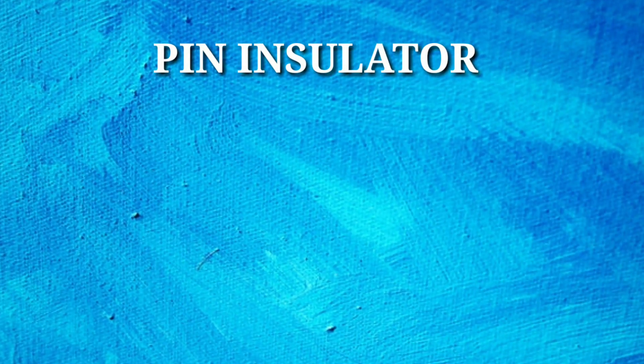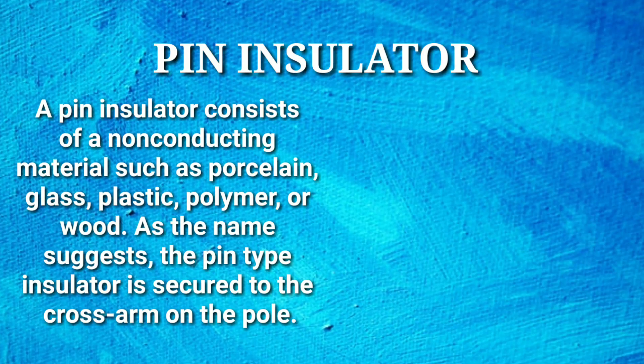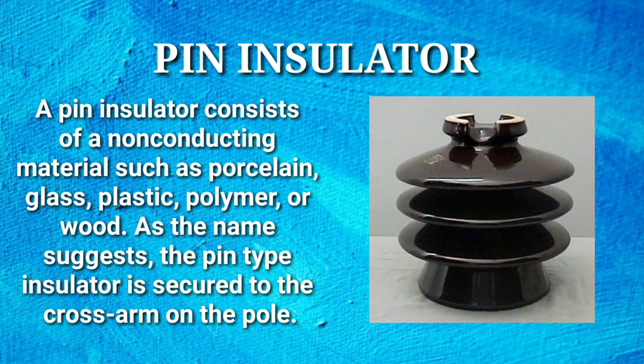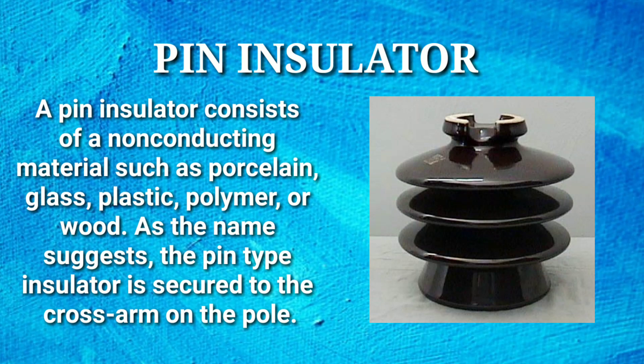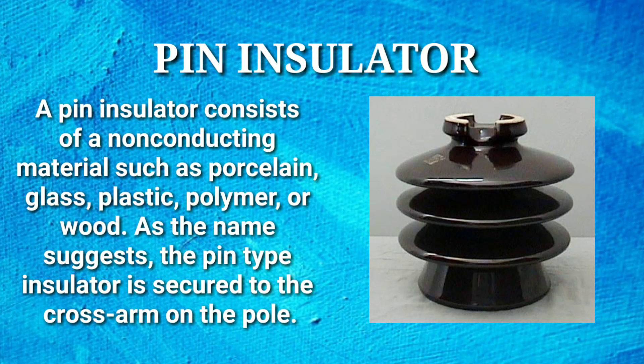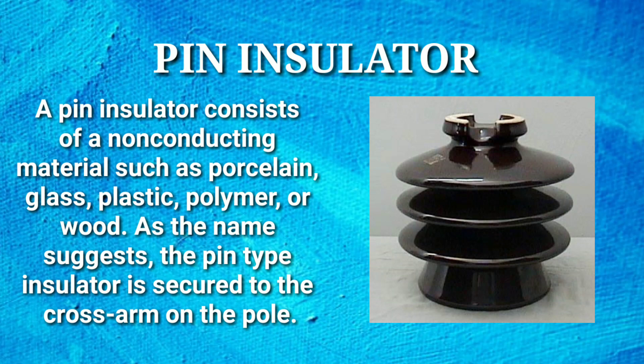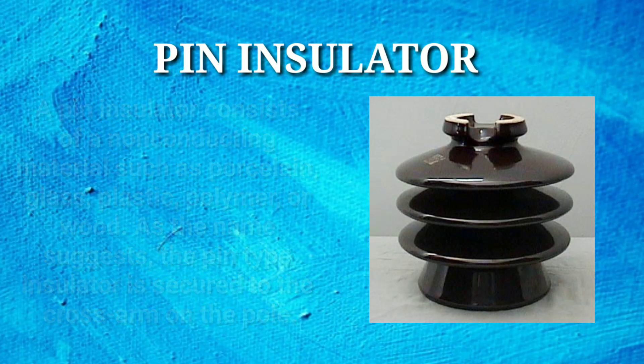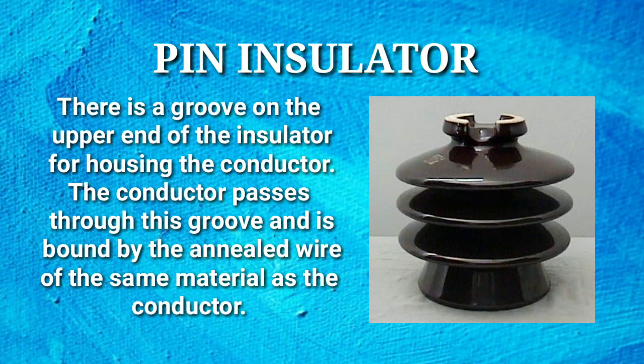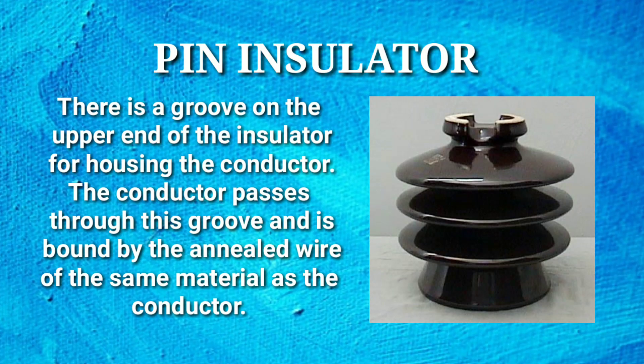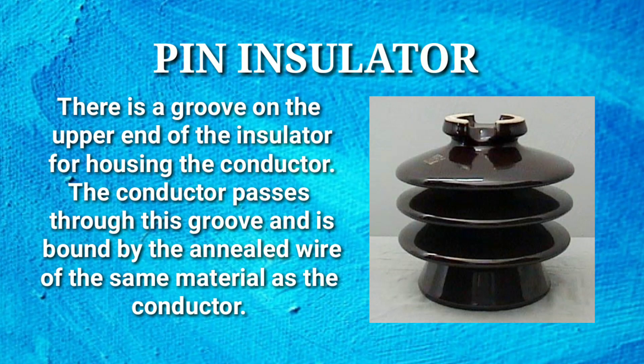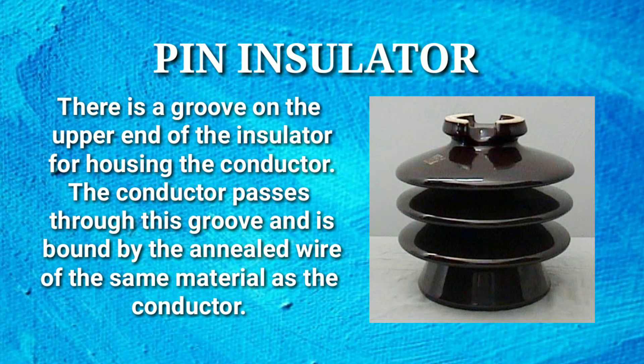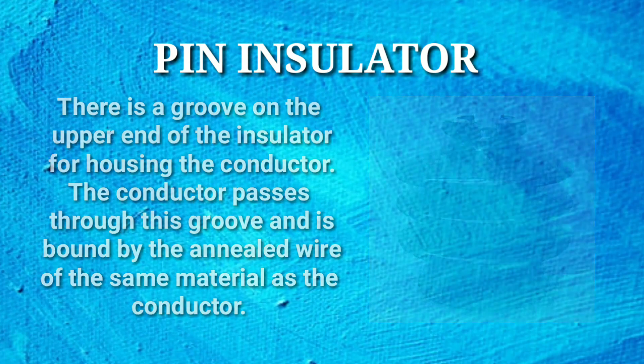Pin insulator: a pin insulator consists of a non-conducting material such as porcelain, glass, plastic, polymer, or wood. As the name suggests, the pin type insulator is secured to the cross arm on the pole. There is a groove on the upper end of the insulator for housing the conductor. The conductor passes through this groove and is bound by the annealed wire of the same material as the conductor.